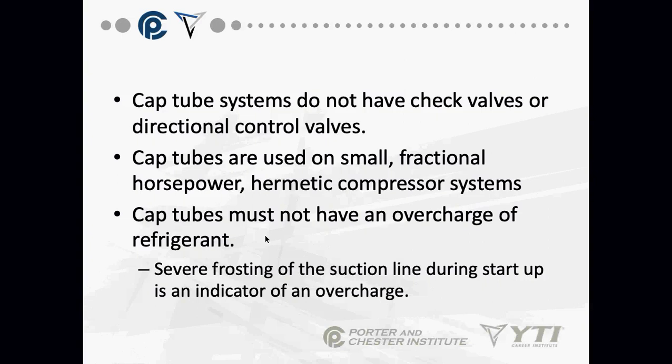Severe frosting of a suction line during the startup is an indicator of an overcharge of refrigerant. Think of this as a troubleshooting tip, guys. Severe frosting of a suction line during the startup of a cap tube system is an indicator of a refrigerant overcharge.